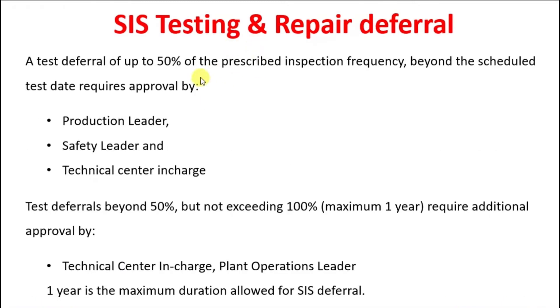SIS testing and repair deferral approval levels: a test deferral of up to 50 percent of the prescribed inspection frequency beyond the scheduled test date requires approval by the production leader, safety leader, and technical center in charge. Test deferrals beyond 50 percent but not exceeding 100 percent, up to a maximum of one year, require additional approval by the technical center in charge and plant operations leader. One year is the maximum duration allowed for SIS deferral.